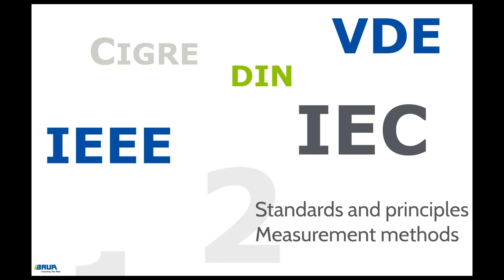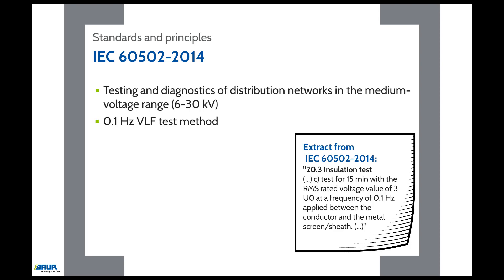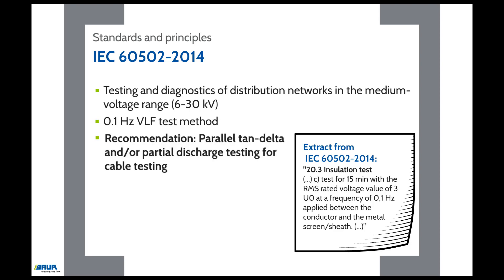IEC 60502, 2014 covers, among other things, testing and diagnostics for distribution networks in the medium voltage range from 6 to 30 kV. An update to the standard led to the inclusion of the 0.1 Hz sinusoidal VLF test method and the recommendation of TAN-delta and/or partial discharge testing to accompany cable testing. The simple DC test for plastic cables was removed from the standard.